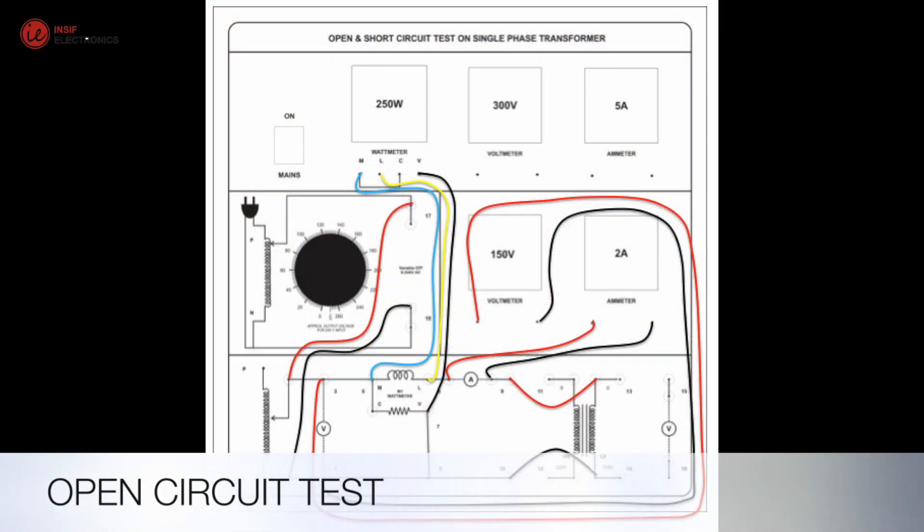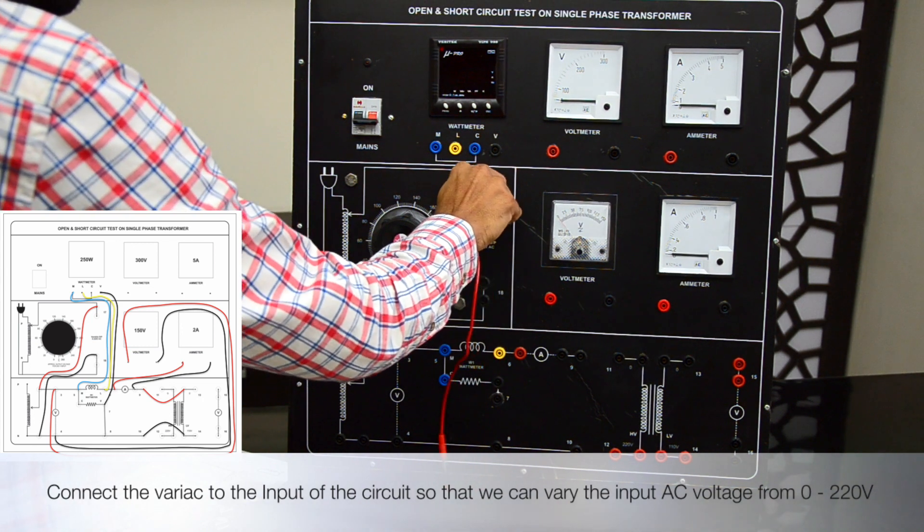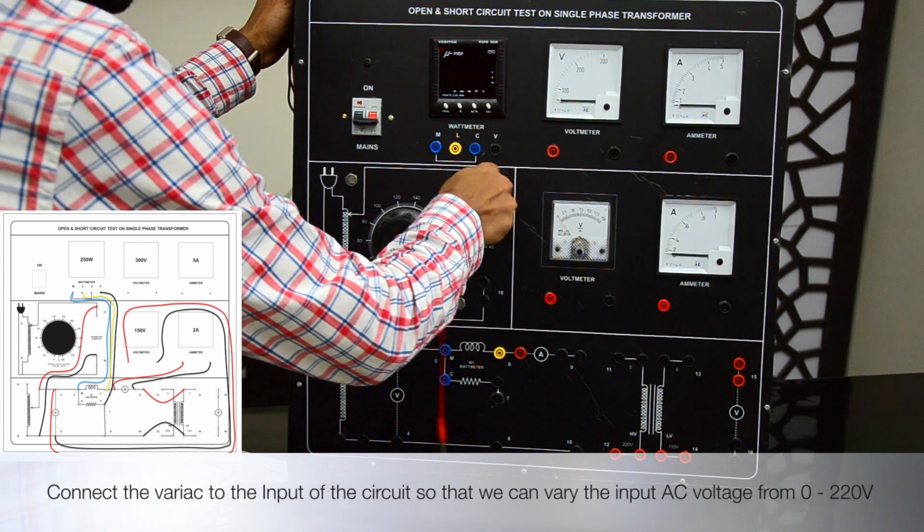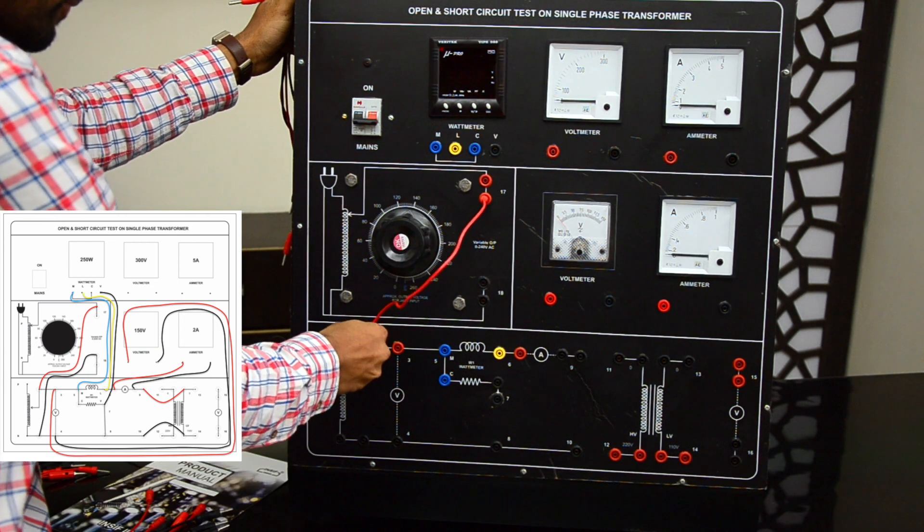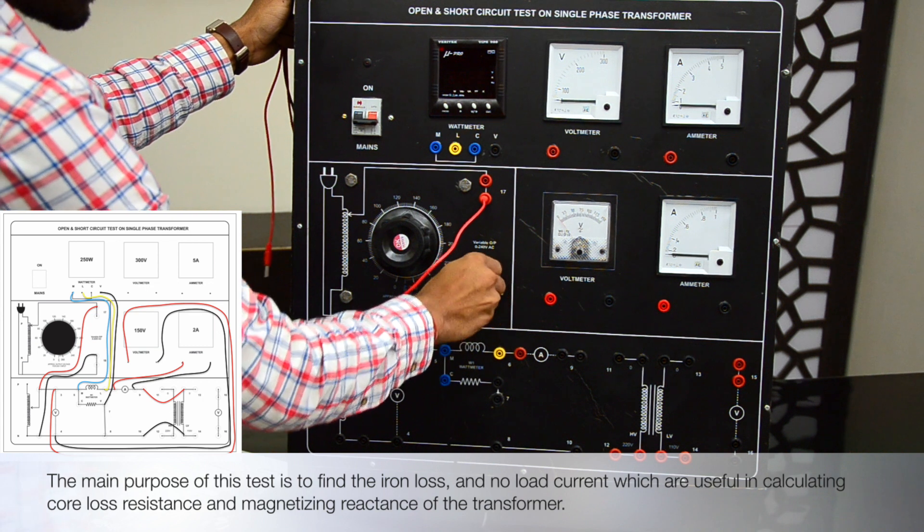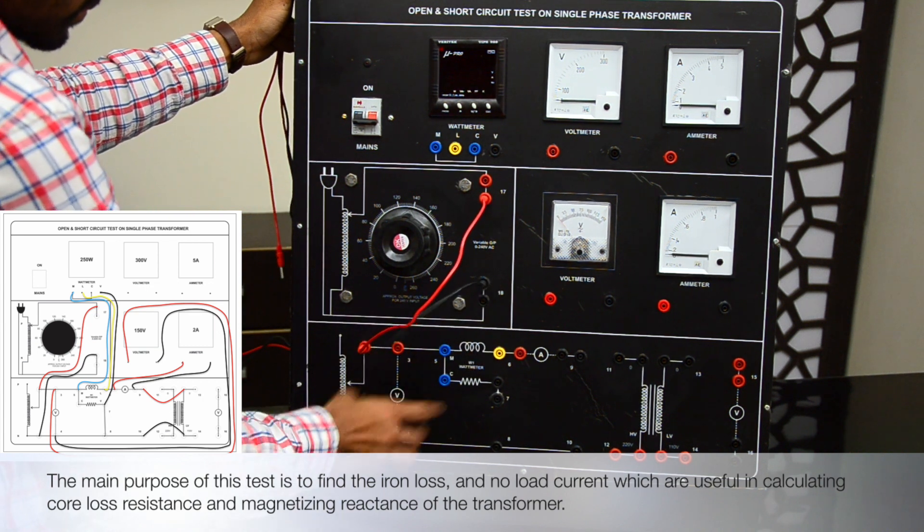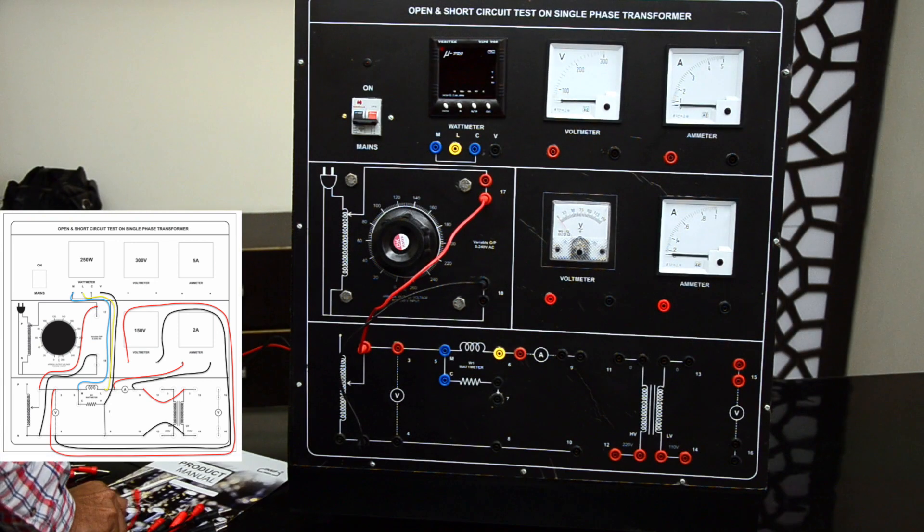Let's begin with the connections of open circuit test. Connect the variac to the input of the circuit so that we can vary the input AC voltage from 0 to 220 V. The main purpose of this test is to find the iron loss and no-load current, which are useful in calculating core loss resistance and magnetizing reactance of the transformer.